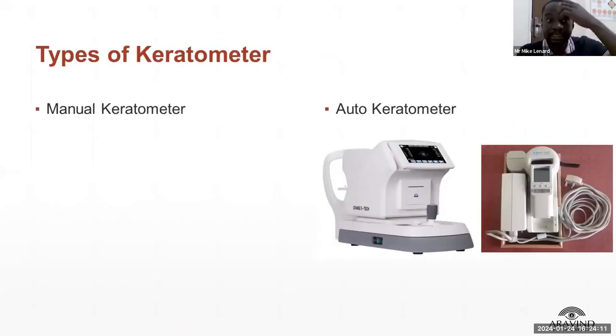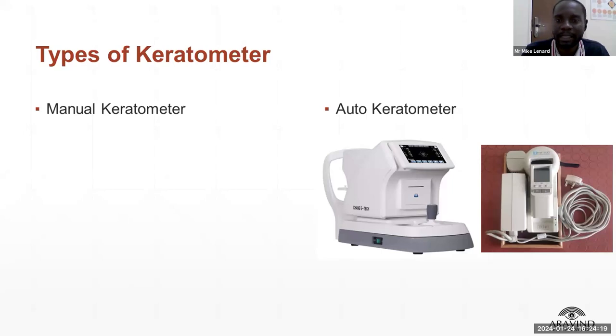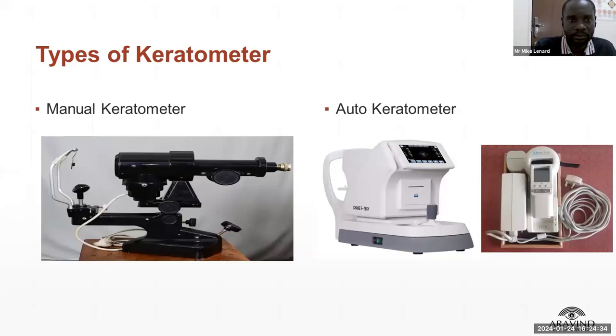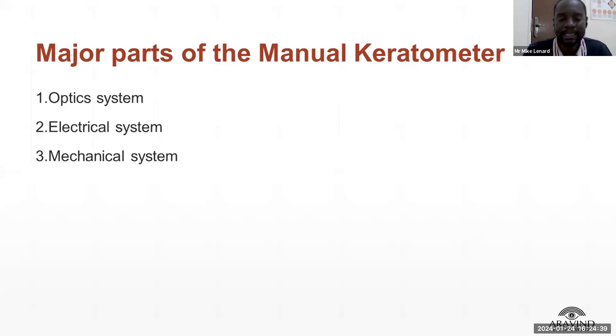Keratometers are in two categories: we have a manual keratometer and an auto keratometer. In this session, we focus on the manual keratometer. The manual keratometer has three major systems: optical, mechanical, and electrical.